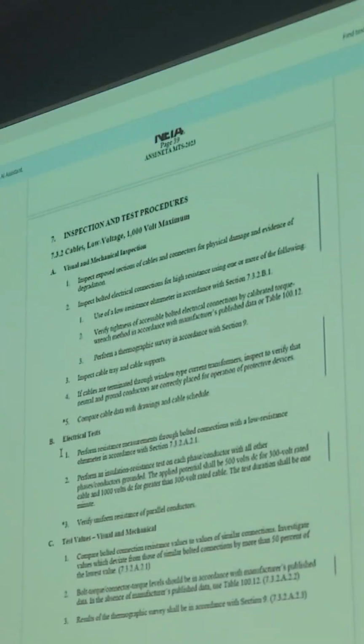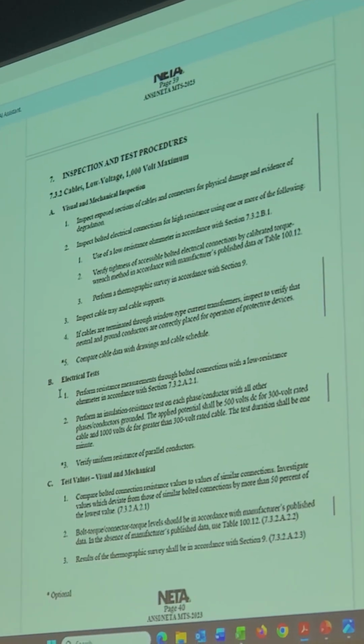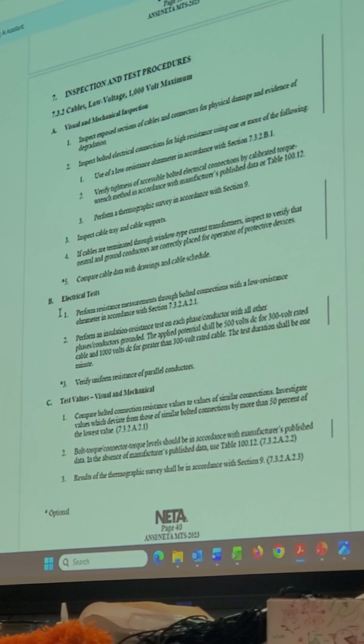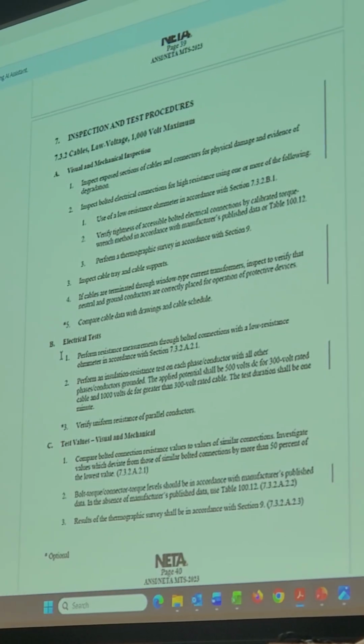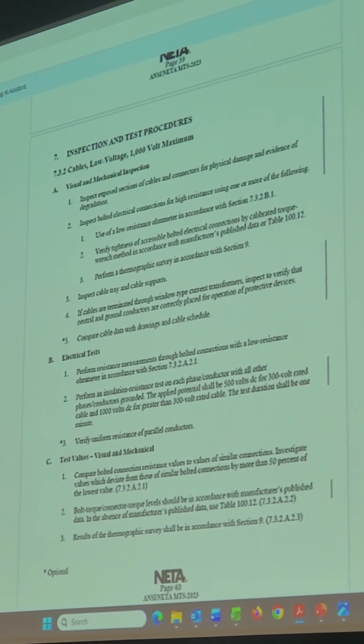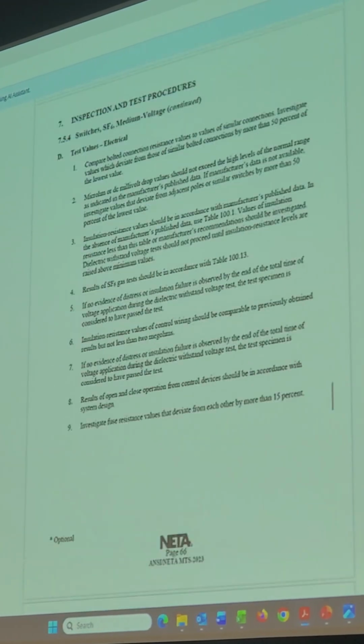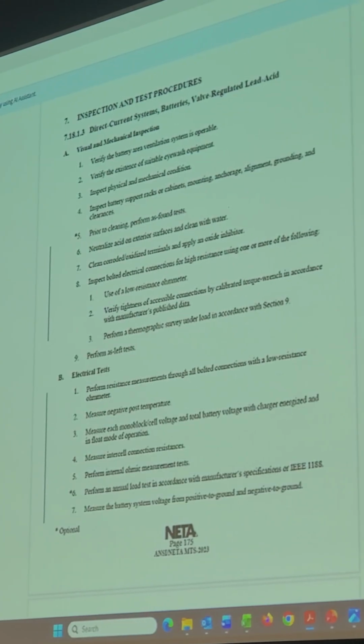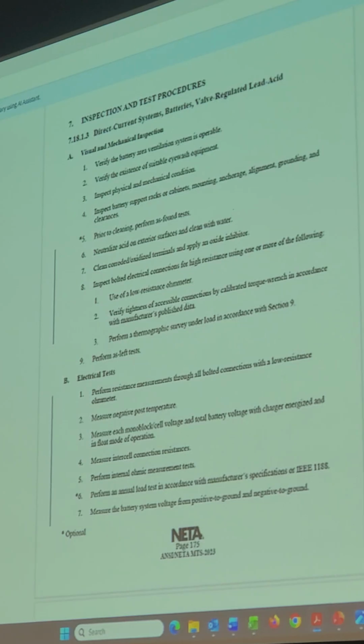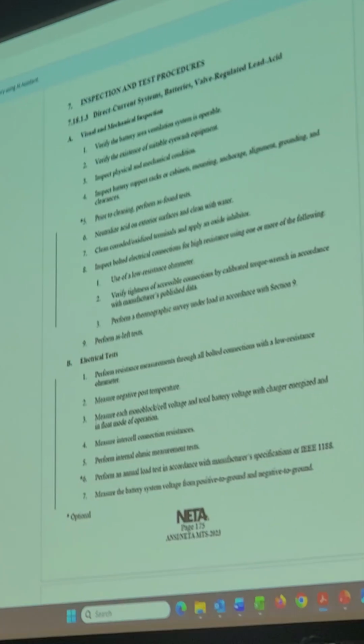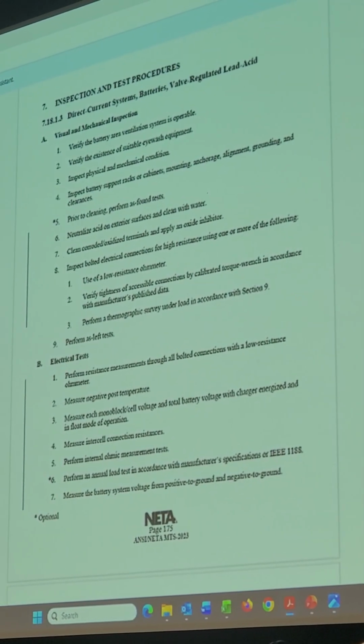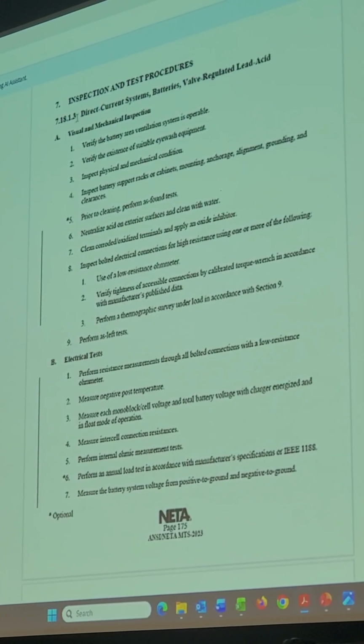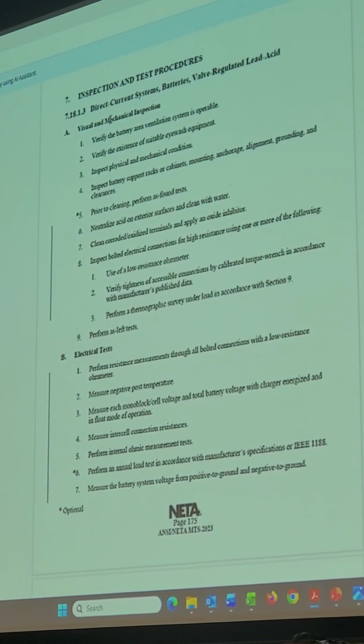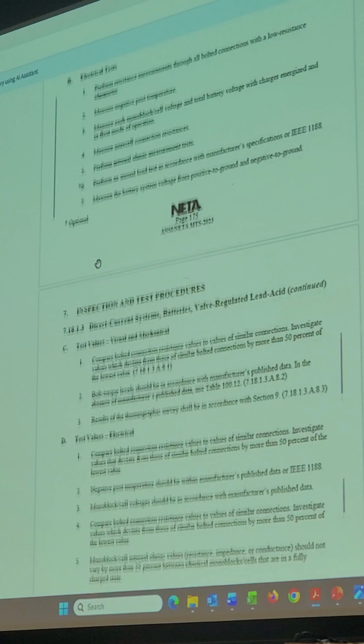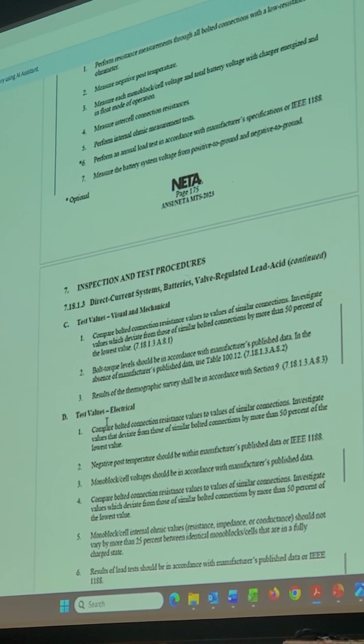This is just to give you the overall sense of how this book is trying to give you almost a procedure, to influence your decision making and allow you to perform the electrical tests necessary for each component. Let me take a wild example here, I'm just going to go to a random section. Spin the wheel. Now we're looking at direct current system batteries, valve regulated lead acid, or VRLA type. This is not a battery class, but you'll notice that even for an unrelated piece of equipment, and those of you in the other classes have seen this in the transformers and switchgear sections, it follows the exact same progression: A is visual mechanical inspection, B is your electrical test, C is your test values for visual mechanical, and D is your test values for electrical.